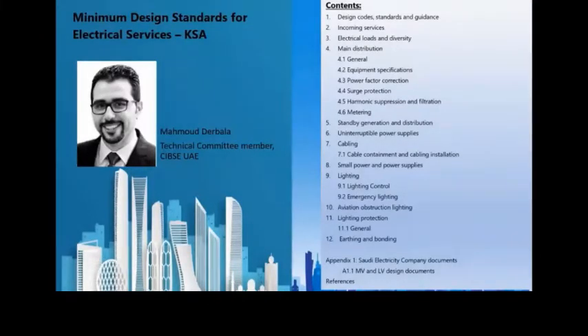In terms of incoming service, which is Chapter 2, it explains how services are brought to the building and the supply characteristics: the medium voltage system, 33 kV or 13.8 kV in Saudi Arabia; the low voltage system, which is 400 volts 3-phase and 230 volts single phase; 60 hertz, which is the frequency in Saudi Arabia; fault level, power factor value, and the voltage drop limitation. The section provides the information required on how supply characteristics are derived.